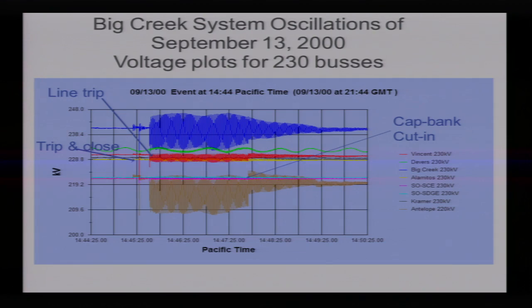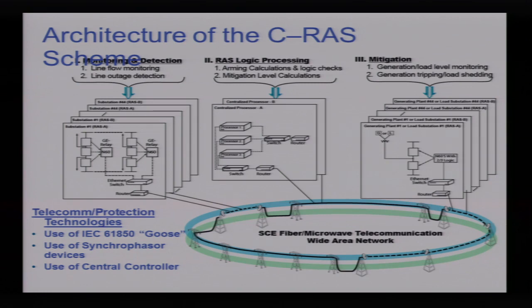Synchrophasors allow us to detect that. The schemes to detect and remediate these are called remedial action schemes. This is one being developed right now by Southern California Edison, and it will span the entire southern portion of California. The scheme is straightforward: on the left-hand side are monitoring devices that monitor the status of power lines, whether open or closed, and whether they're overloaded. This information goes to a logic processor, which does basic logic that says if this line's overloaded, and this line is overloaded, and this line trips out, take action. The action right now is shedding load, and these are the mitigation devices connected to the distribution feeders that go and shed load.